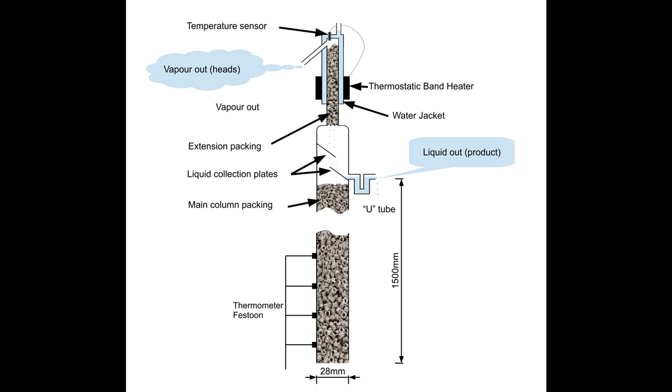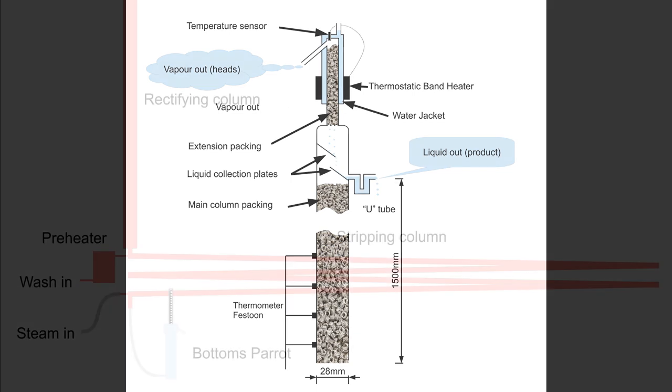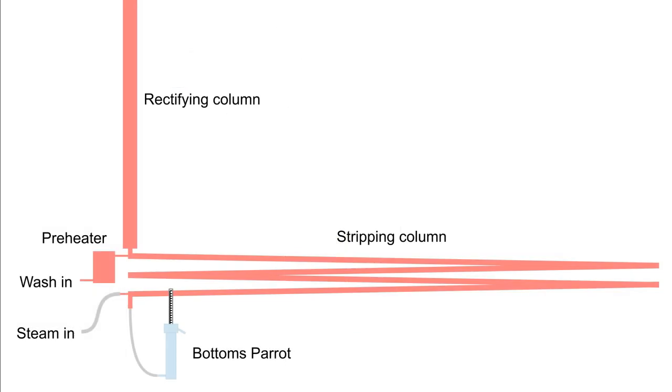Heat is delivered to the bottom of the stripping column as steam, so it could be reckoned in grams of steam per minute, but I have reckoned it in watts of power delivered to the column as specific latent heat of vaporization of water. That's 2.26kJ per gram, so 1 gram per second gives 2.26kW, and 443 micrograms per second or 26.6mg per minute is 1 watt.